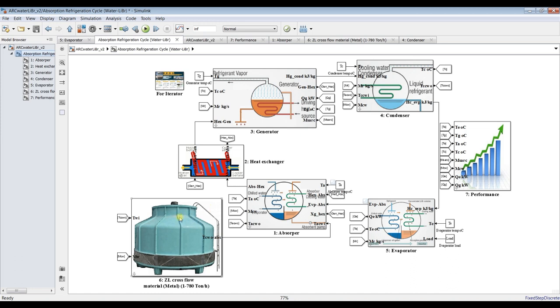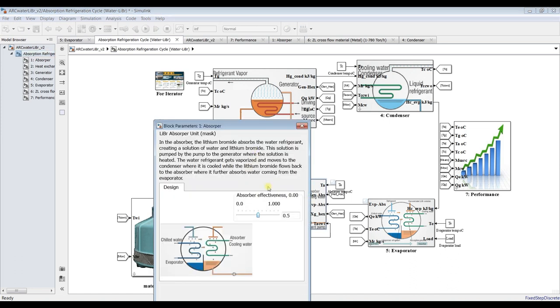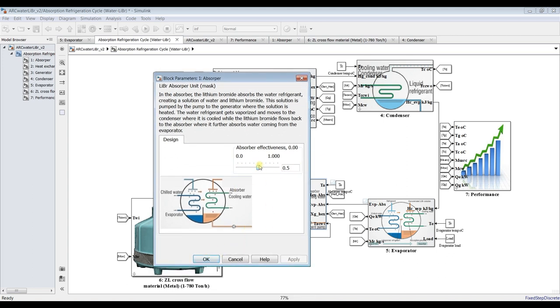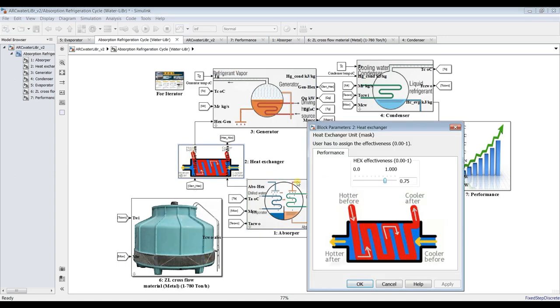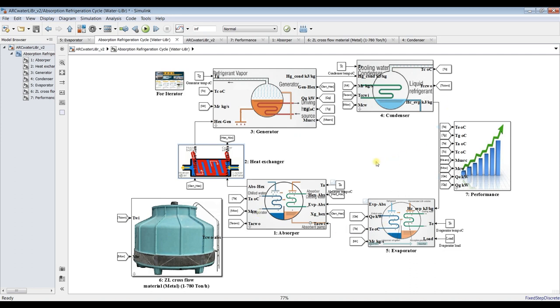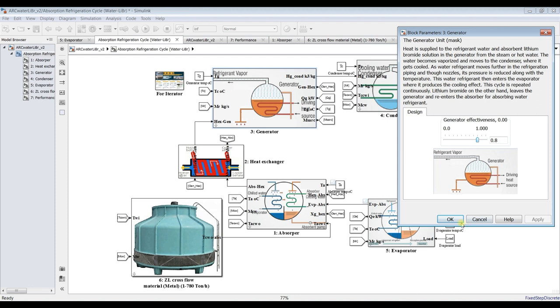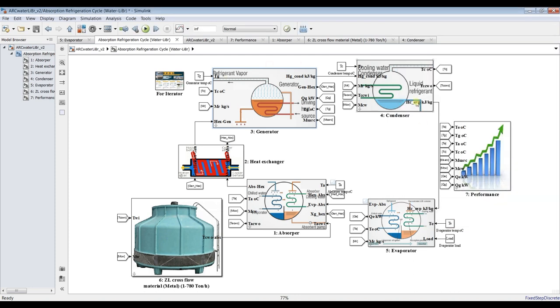We have to assign some individual operating conditions for each unit — assign your absorber effectiveness. You can control your effectiveness based on your design, because all of these units are some kind of heat exchanging unit. Even the condenser is a heat exchanger between cold side and hot side, and the generator is also a heat exchanger. We are going to calculate the effectiveness of the condenser, the cooling water input to the cycle, and the evaporator, controlling the load and calculating the effectiveness.